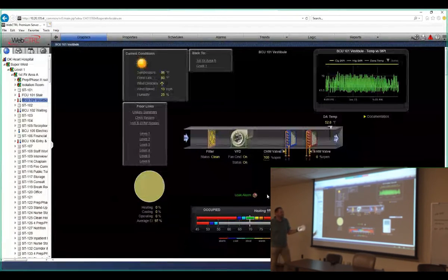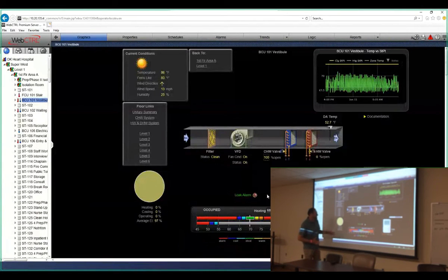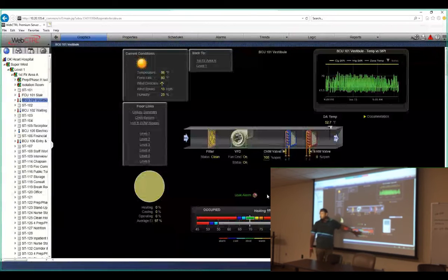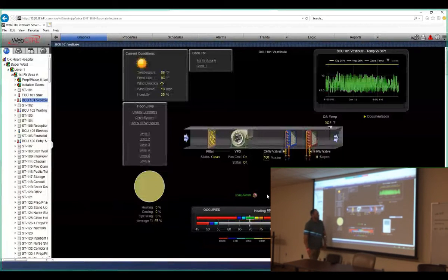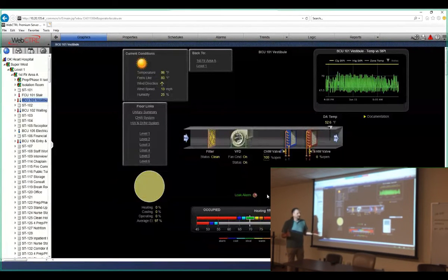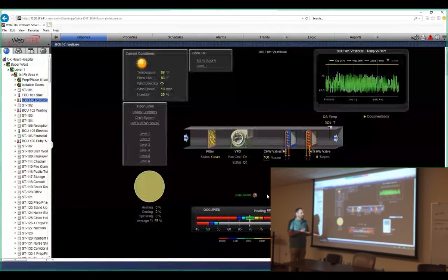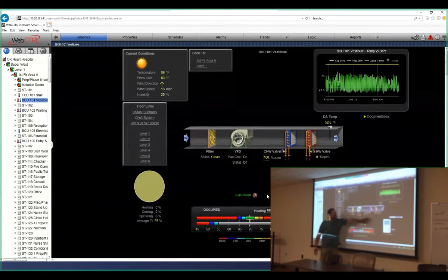So the blower coil unit is really pretty simple. It follows the same temperature controls, just like a VAV as far as temperature. We have a heating set point and a cooling set point. So in the dead band between the heating and cooling, it should be green. Once we drop below the heating set point, we'll start modulating the hot water valve open.